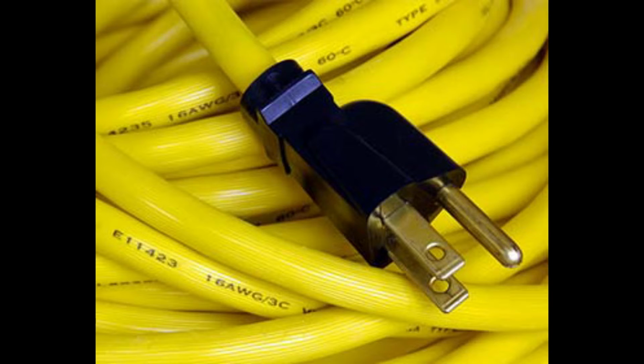Number 3, plug male cord into ground check unit outlet, then plug female cord onto test prong and touch a metal part of the tool to the test prong. The green light will come on if the cord is grounded correctly. Both item 2A and 2B tests are to be completed in one operation.